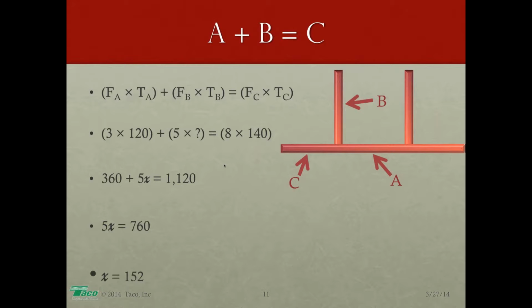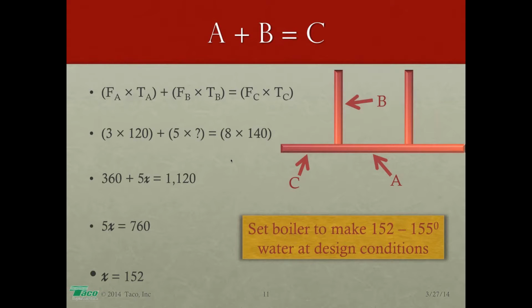Now, could we have guessed at that? Yeah. You might have guessed high, you might have guessed low, but it's always good to know, isn't it? So what we'll wind up doing is setting the boiler's target temperature under design conditions to anywhere between 152 and 155 degrees for heating. You know, 155 might give you a little bit of safety, a little bit of extra. Okay? Now that's the hard way to do it.